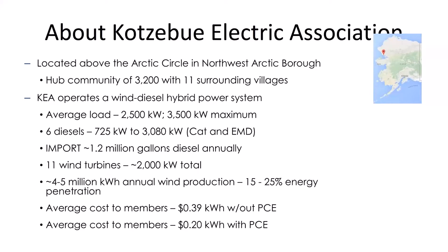A little bit about us: we're the hub of the Northwest Arctic Borough, 3,200 people with 11 villages around us. Since 1997 we've had a wind diesel hybrid system. Our average load is 2,500 kW, to a maximum of 3,500 kW. Our minimum in the summer is probably about 1,500 kW. We've got six diesel generators of different sizes that we can dispatch based on how much load we're trying to supply for the town and the time of year.